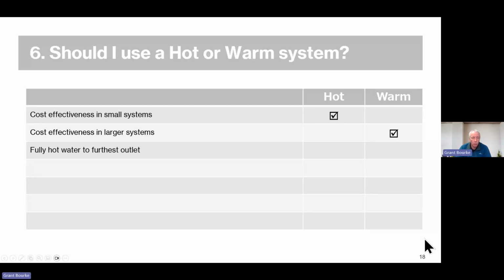Getting fully hot water to the furthest outlets, obviously a hot water system is better for that. With the warm water system, we need to insulate really well to make sure that the person at the furthest fixture isn't getting water that's not of a temperature that they feel is usable. Very hot water to the kitchen sink, obviously the hot water system does that better. With the warm water system, as we saw on the previous slide, we can add a boost to it by putting a small electric tank in, but it all adds cost.